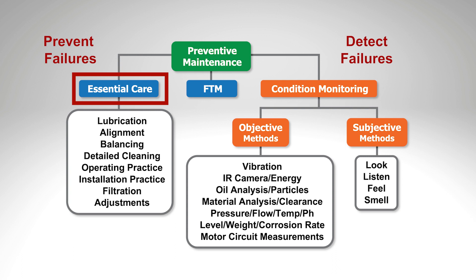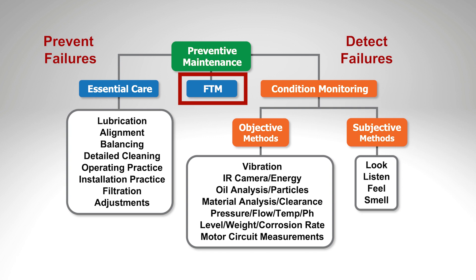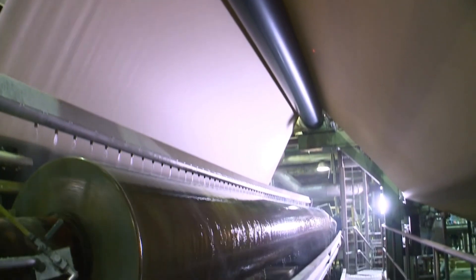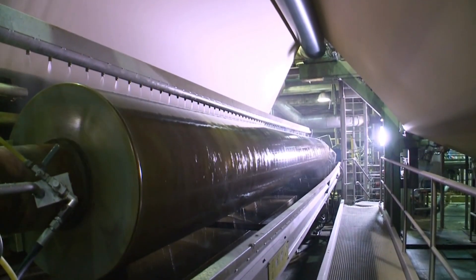You can prolong or shorten equipment life based on how well we do these things. The little box in the middle, FTM, stands for fixed time maintenance. Another way to prevent failures is simply to change out the equipment. You can run a motor for a couple of years and just change it out, assuming you know its life — though a motor is probably a bad example because we don't know the life of motors. But some people take, for example, felt on a paper machine and change it out every six weeks because they know that life is roughly six weeks.